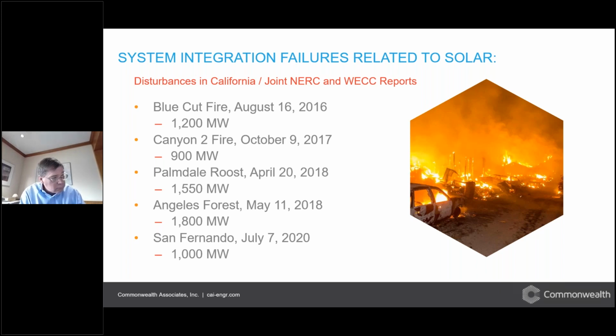Various reasons why the inverters were not able to ride through these system disturbances. Sub-cycle transient overvoltages. The inverters were not set correctly to ride through these incidents. AC overcurrent. There were a number of issues, like DC reverse current in the inverter.